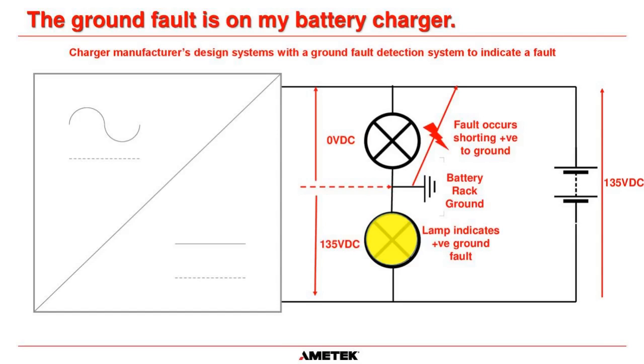So if you have a ground fault, all you're doing, on this one here, is tying the DC bus, the positive, to the ground. Because there is no current flow, it's not going to cause any problems. So now on this circuit, the positive is connected to ground. What will happen now is if you have a negative ground after you have a positive ground, then you will have a direct short circuit, which can cause fires or cause breakers to trip. But a single fault on a DC system is not going to cause you problems.